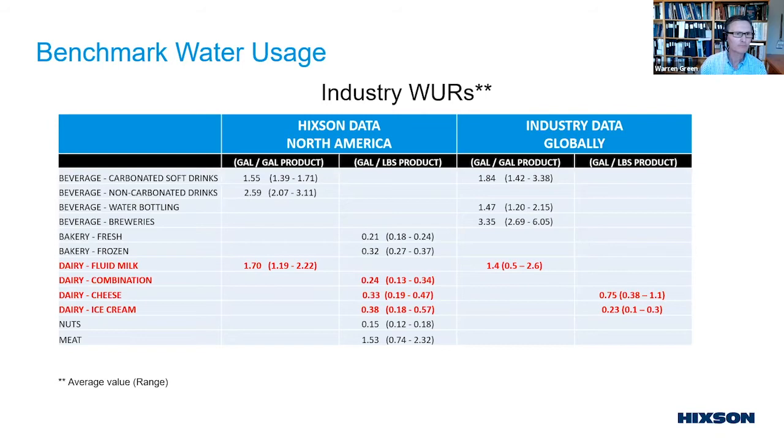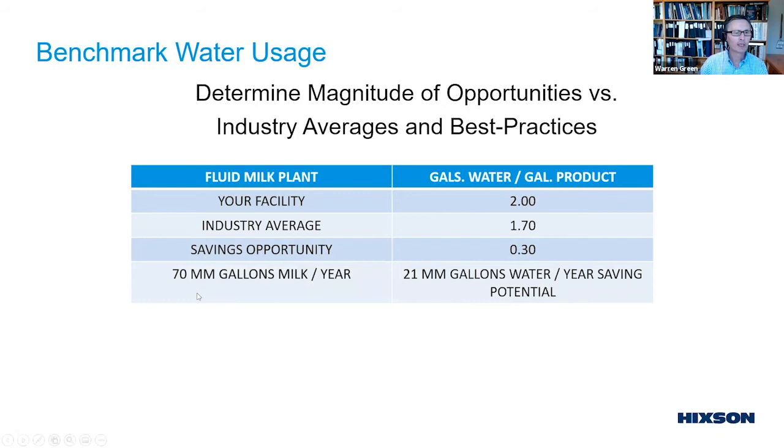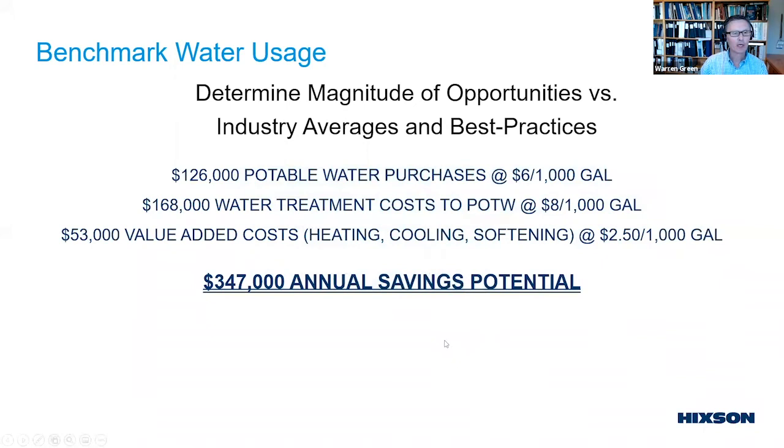For example: if your facility is buying about 2 gallons for every gallon produced, compared to Hixson's North American average of 1.7, you have an opportunity of about 0.3 gallons per gallon. For a 70-million-gallon-per-year milk plant, that's almost 21 million gallons of water per year you could potentially save just to reach the industrial average.